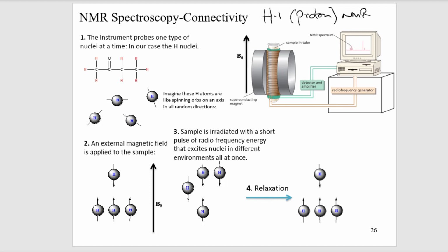We have two of them at RIT. One is a 300 megahertz NMR, and that's based on the size of the magnet. We also have a 500 megahertz. These go way up in cost. NMR instruments are costly to run, too. The magnets have to be cooled with liquid helium and liquid nitrogen, and that is costly and has to be done weekly on a schedule. So there's a lot to them, okay?